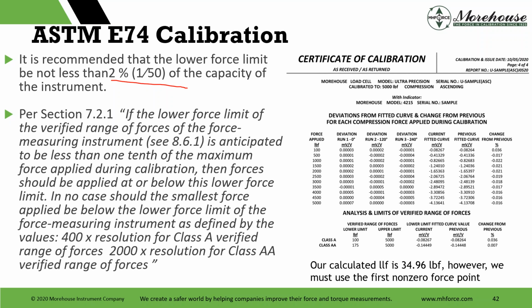For section 721, if the lower force limit of the verified range of force measuring instrument is anticipated to be less than 1/10 of the maximum force applied during calibration, 10%, then forces should be applied at or below this force limit. In no case should the smallest force applied be below the lower force limit of the force measuring instrument as defined by 400 times the resolution for class A verified range of forces, 2000 for AA. So that's another one. This report had class A and AA. Therefore, we've got to take 2000 times that resolution, which is around 50 some.